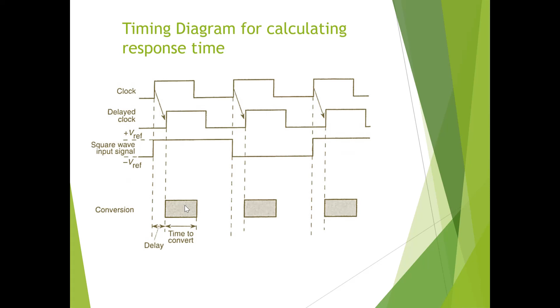You can use this setup for transient response to measure the ADC's recovery time to overvoltage. Set just one of the reference voltages, plus V reference or minus V reference, to its maximum over range value, and set the other references to a value near full scale in the opposite polarity or direction. Adjust the conversion delay until the output gives the valid value, and the delay equals the overvoltage recovery time. Now, overvoltage recovery we have seen.